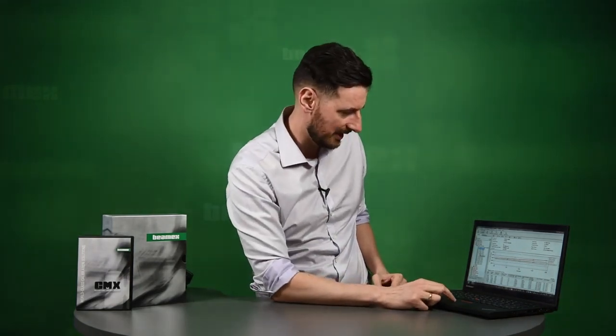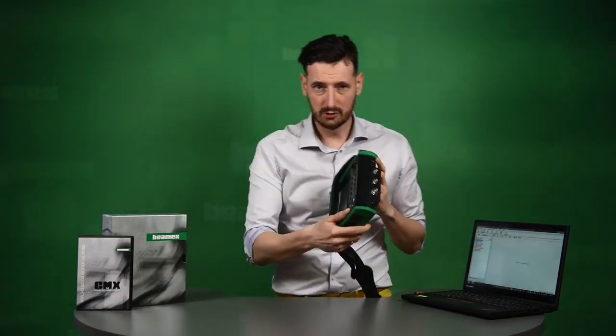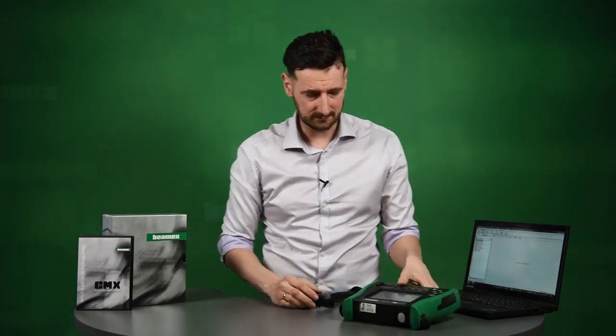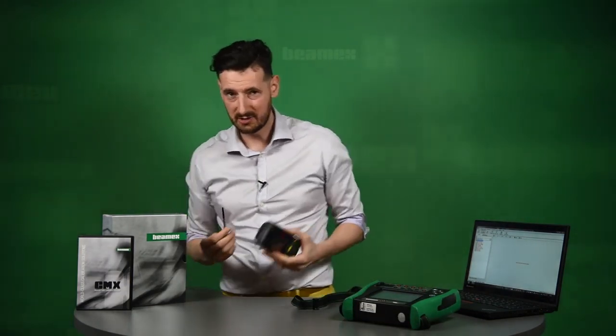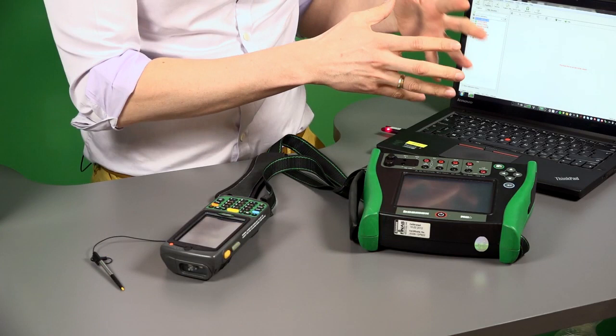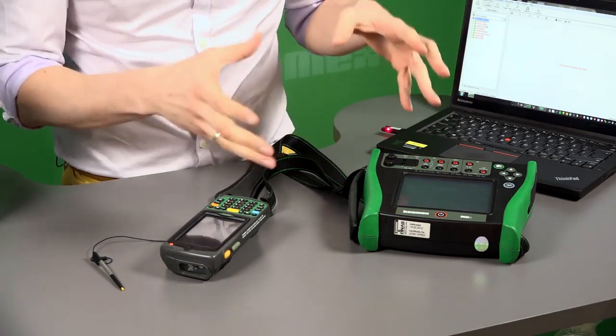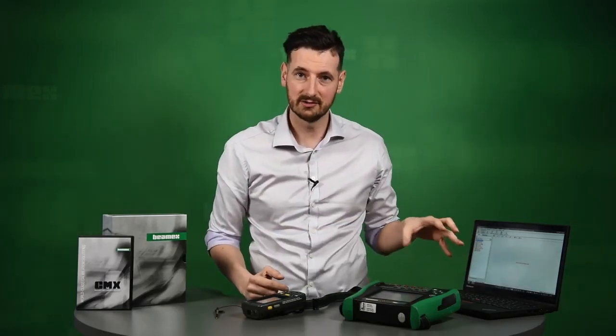A normal, typical day would look as if you go into the CMX, you choose the ones that you want to do that day, you go into the list, you select the positions that you would like to calibrate that day, and then you transfer them from CMX to a portable calibrator or a mobile device. It all depends what you need. You could use an MC6 calibrator, or you can use a mobile device like this PDA. You send the information from CMX to the mobile device or portable calibrator. You perform the calibration, and then you receive the information back to CMX.